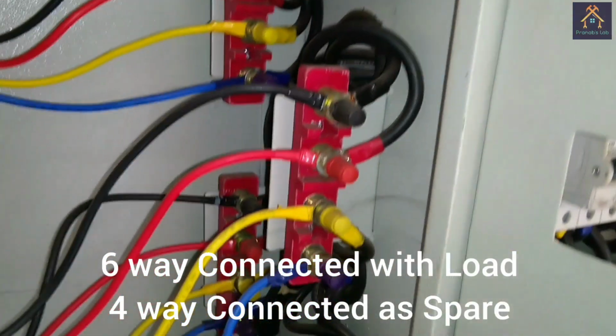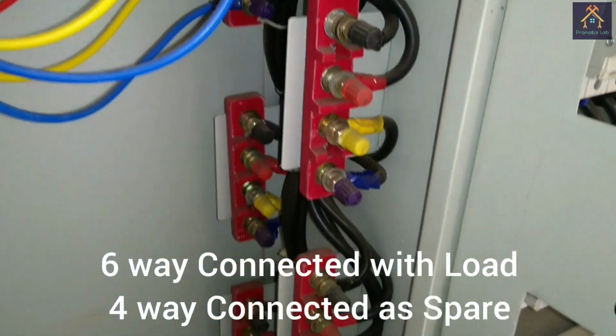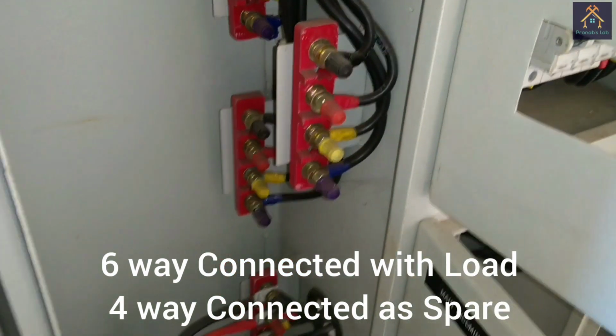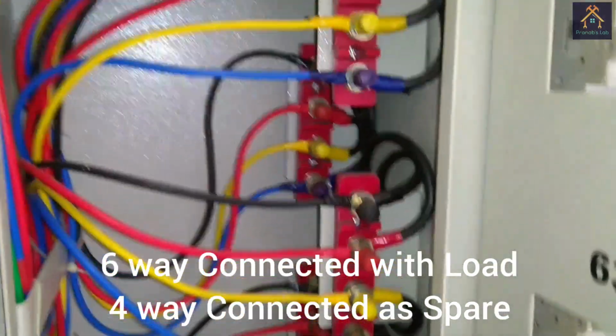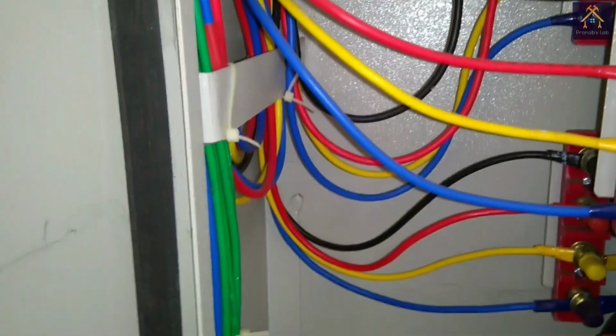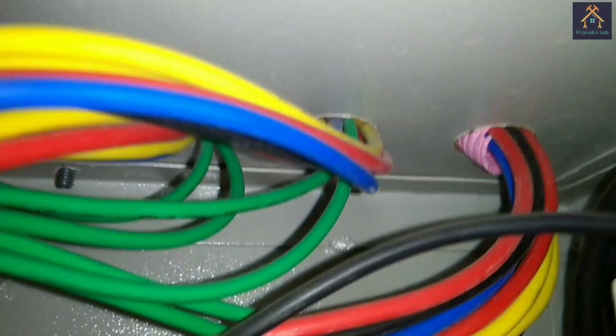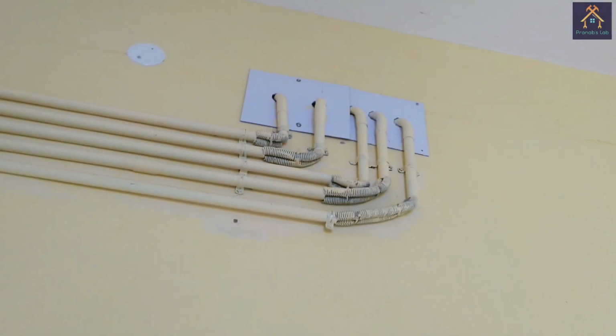You can see the 10 ways are connected with 10 different connectors, and there are a total of 4 connectors which are not actually connected with the load. That means the 4 MCBs are the spare MCBs. The cables coming out from the terminals are inserted into the flexible conduit pipes. The different ways are run through the 3 different conduit pipes and went out from the room.